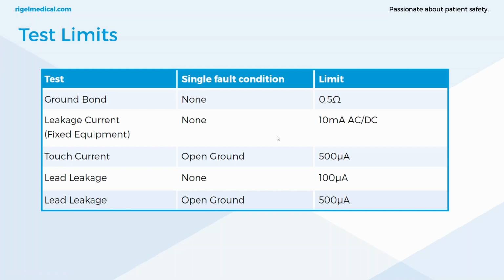So here's just for some clarity on the tests, their limits and single fault conditions. They're there clearly in the code, but it might be useful for you to have. So this is the 2021 limits. Print a copy, stick it on the wall. Good for a quick point of reference if you need it, especially if you're using a manual tester and you've got a new biomed that's not entirely sure of the limits and fault conditions. This gives you a bit of an idea of how it's performed.